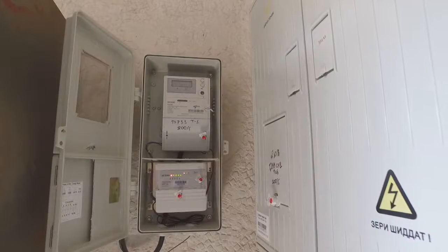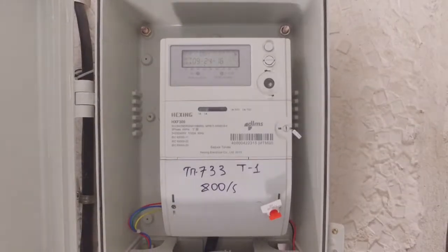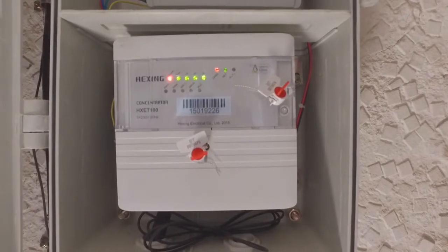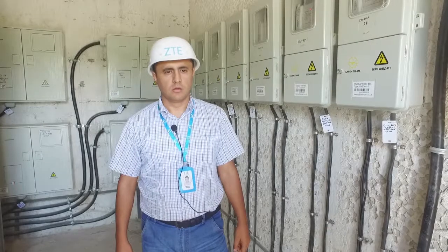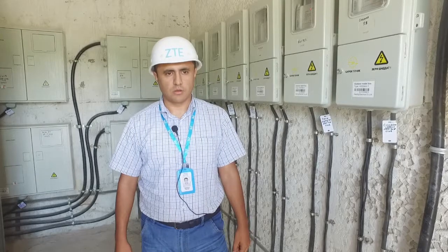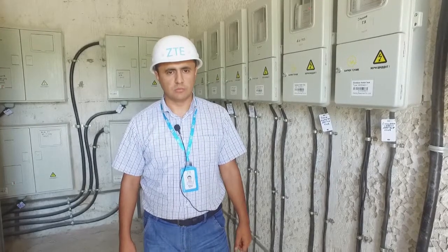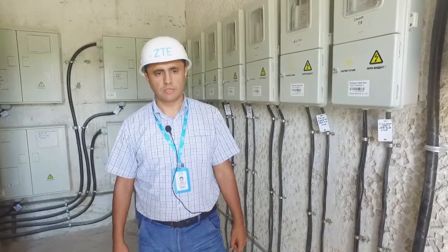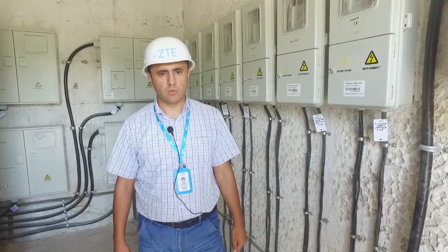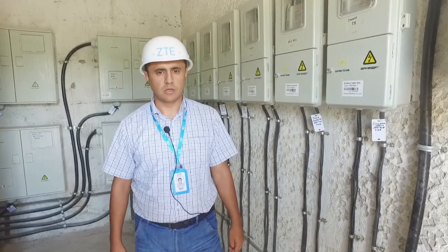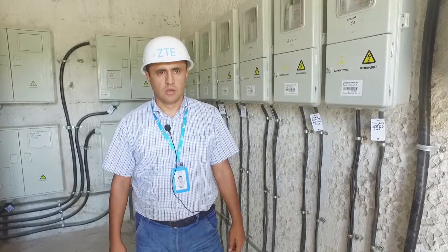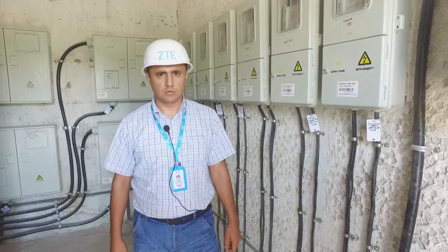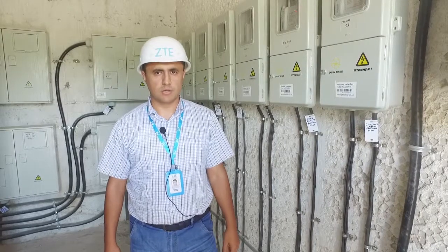The bulk meter consists of 4 main parts: bulk meter, data concentrator, current transformers, meter box, etc. Our bulk meter operates through a CT, current transformer, which transforms big current into small current. For example, our 3-phase bulk meter's nominal current is 10 ampere. The counted total consumption data is sent to the data concentrator through an M-bus wire connection.